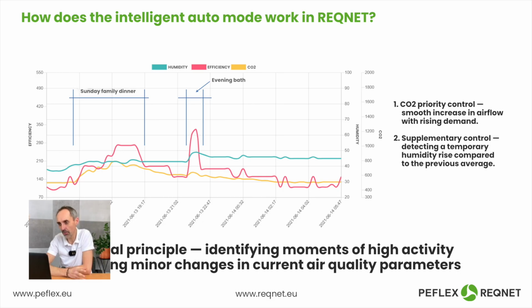However, when it comes to the humidity sensor, the device measures the humidity and calculates an average over several hours. But when there is a sudden spike, an increase in humidity greater than that several-hour average, that's when the device starts to react. So it starts removing the excess moisture until it reaches that, let's call it, averaged value.